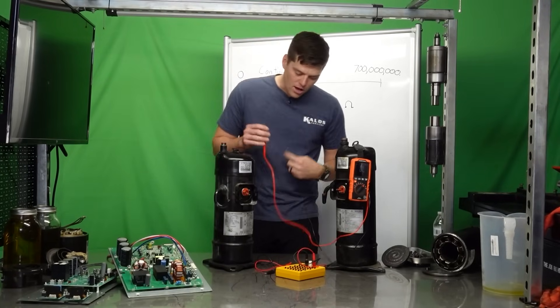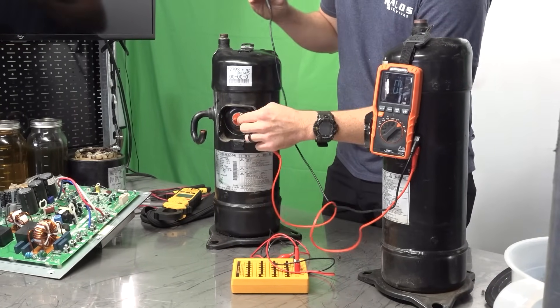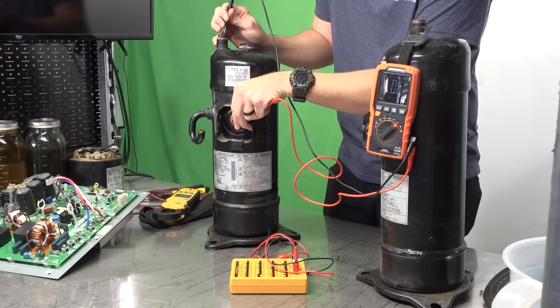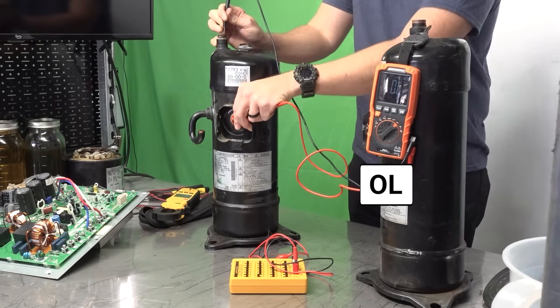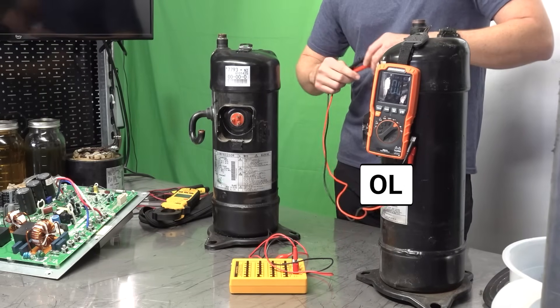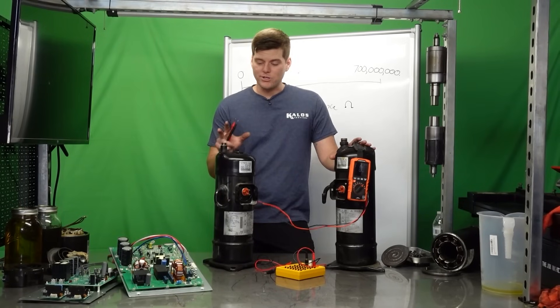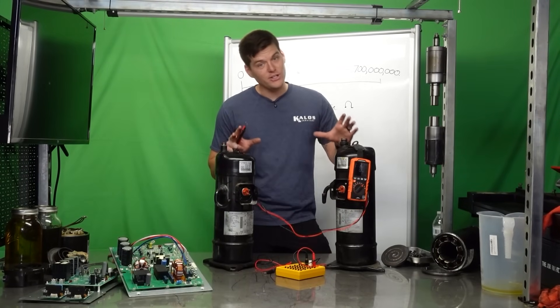Now let's jump over to this other compressor. I'm going to do the same thing and check in the same spots as you should. And with that, I'm going to get no satisfactory beep, and also it says OL. Now, if I was out in the field and it's a Friday, and man, I really got to get going, I've got one bad compressor, and this one's good. But the joke's on you because they're actually both bad.